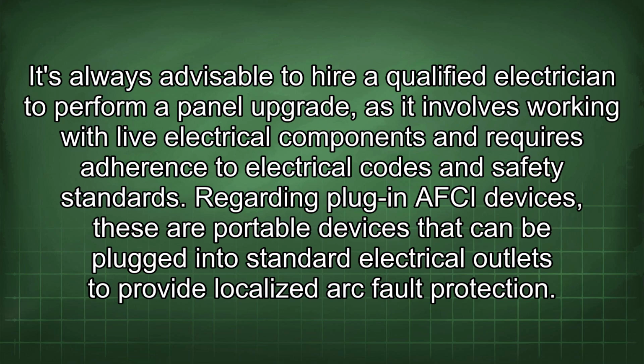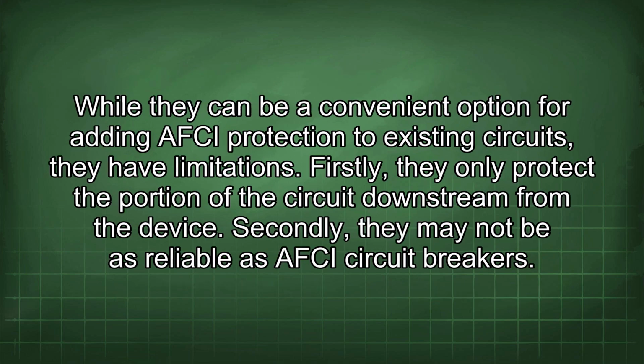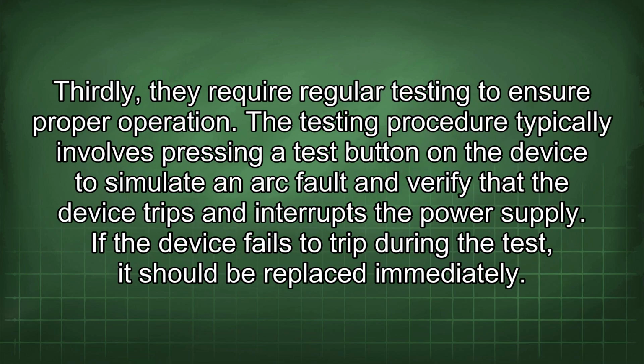Regarding plug-in AFCI devices, these are portable devices that can be plugged into standard electrical outlets to provide localized arc fault protection. While they can be a convenient option for adding AFCI protection to existing circuits, they have limitations. Firstly, they only protect the portion of the circuit downstream from the device. Secondly, they may not be as reliable as AFCI circuit breakers. Thirdly, they require regular testing to ensure proper operation. The testing procedure typically involves pressing a test button on the device to simulate an arc fault and verify that the device trips and interrupts the power supply. If the device fails to trip during the test, it should be replaced immediately.